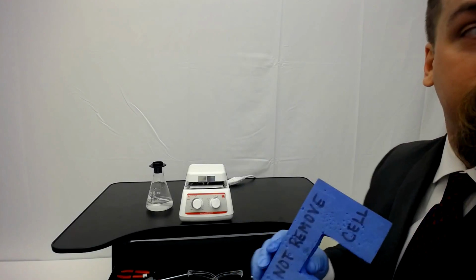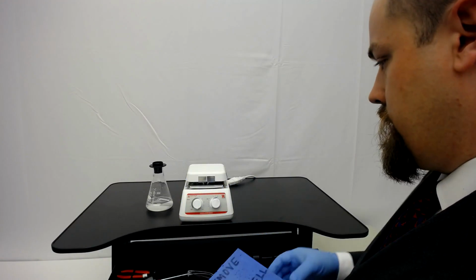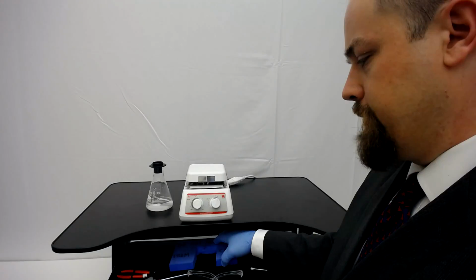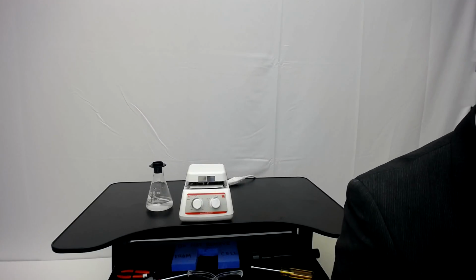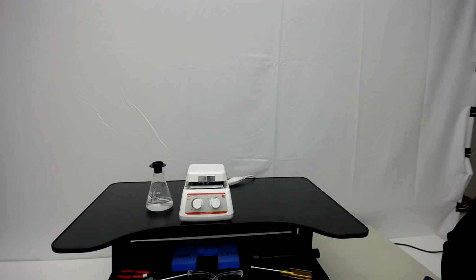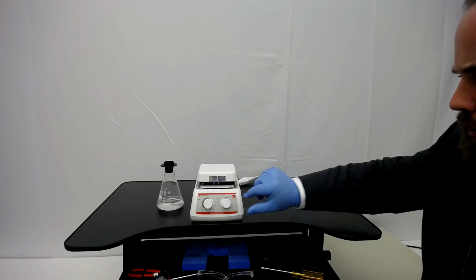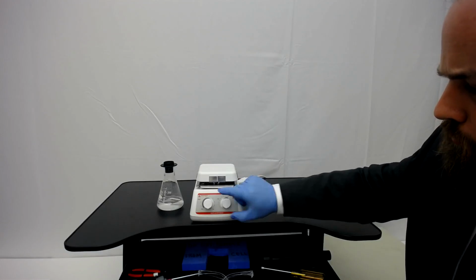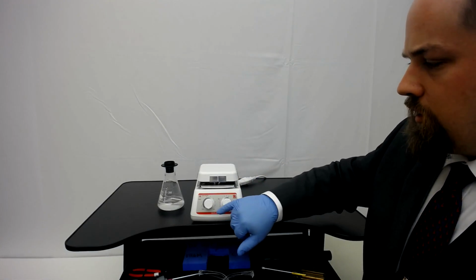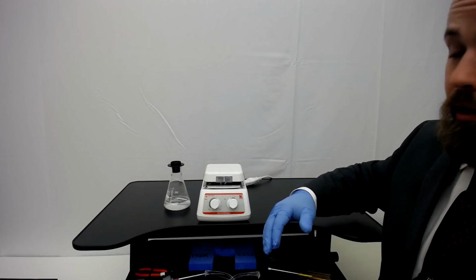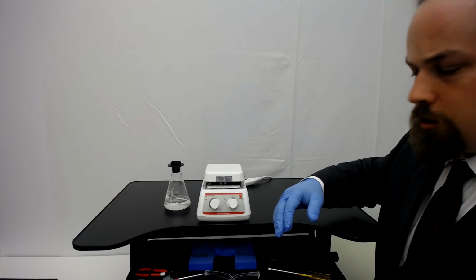And we have a piece of foam for setting the unit on once it's open. For testing, you're also going to need, for heating units, a temperature probe and a hipot insulation tester. So going in and starting to familiarize you with the unit. This is both a heating and stirring unit. It's a hot plate stirrer.